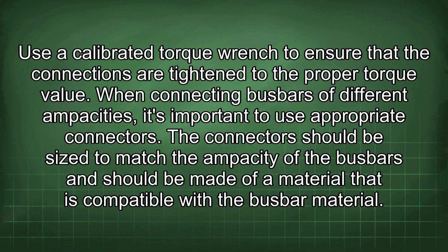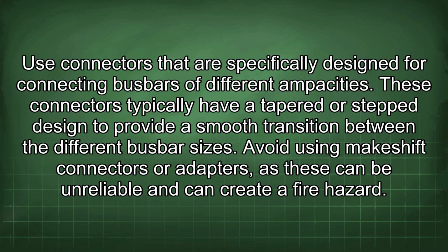When connecting busbars of different ampacities, it's important to use appropriate connectors. The connectors should be sized to match the ampacity of the busbars and should be made of a material that is compatible with the busbar material. Use connectors that are specifically designed for connecting busbars of different ampacities. These connectors typically have a tapered or stepped design to provide a smooth transition between the different busbar sizes.